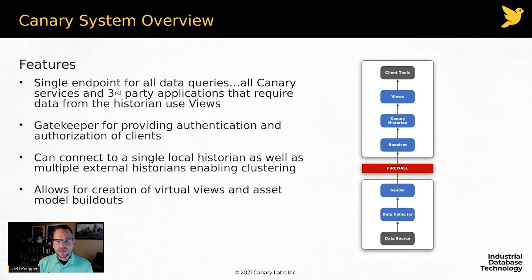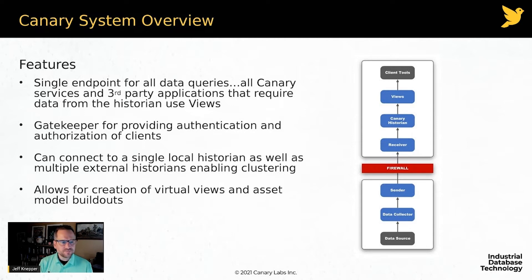You may recall from the last video that you can cluster multiple Canary historians. The historian server supports more than two million tags, but if you have four million tags you might want to stand two historians side by side. By pulling Views onto its own application server, I can connect to two, three, four, five, or more historians and create a cluster so that when making a query as a client, I don't see multiple historians — I just see one large archive.